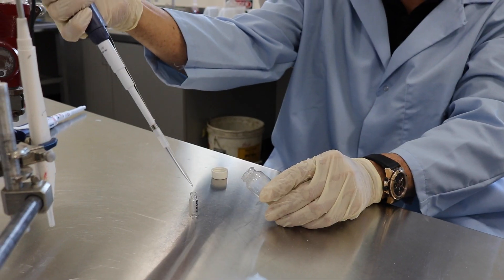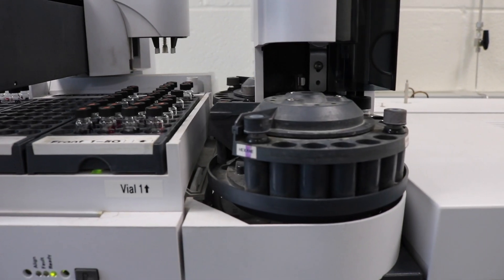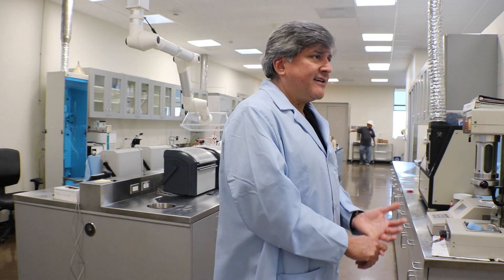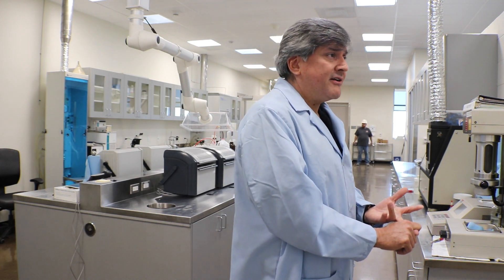The tests are providing our support people and our transmission engineering a means to gauge the life expectancy of our pieces of equipment — mainly moisture tests, dielectric strength, power factor at both 25 and 100.